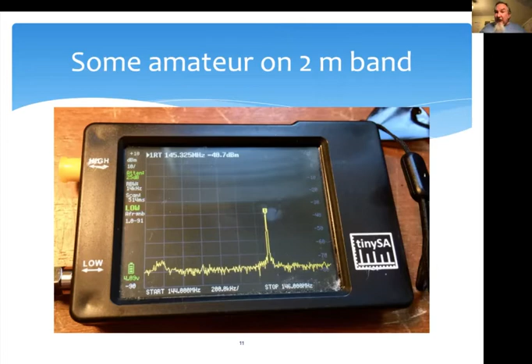The scan time can vary quite a lot. It can be several or tens of minutes, depending on how you set it up. But there are lots of ways to change the bandwidth, change the range that you're looking at, change even the way that it acquires and processes the signal to speed that up, depending on whether you want a rapid display or a very, very accurate measurement over admittedly quite a long period of time. So again, all these adjustments were there. The point I'm making, if I haven't already made it clearly enough, is that the TinySA relies on the user identifying and avoiding situations where there are artifacts and spurious signals on the screen, as do most spectrum analyzers, if the truth be told.